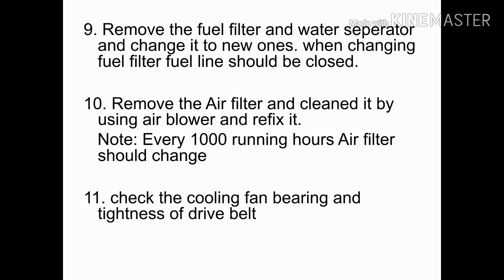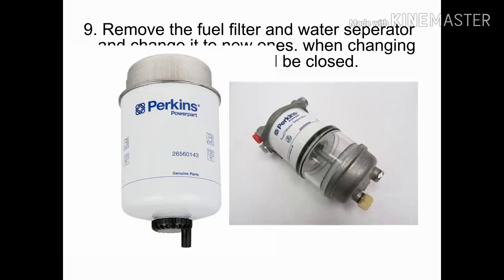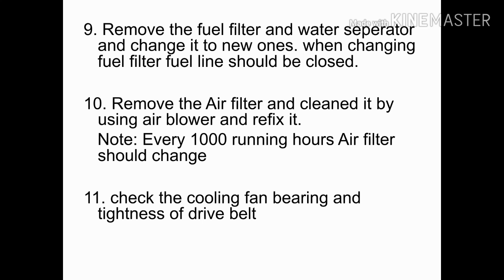The next step is to remove the fuel filter and water separator and change them to new ones. See this picture — this is the fuel filter and this is the water separator. Both filters should be removed and replaced. Important: whenever changing the fuel filters, the fuel line should be closed, otherwise fuel may leak out.